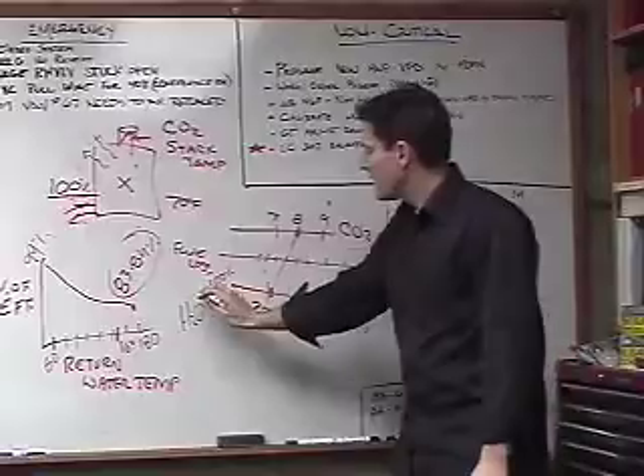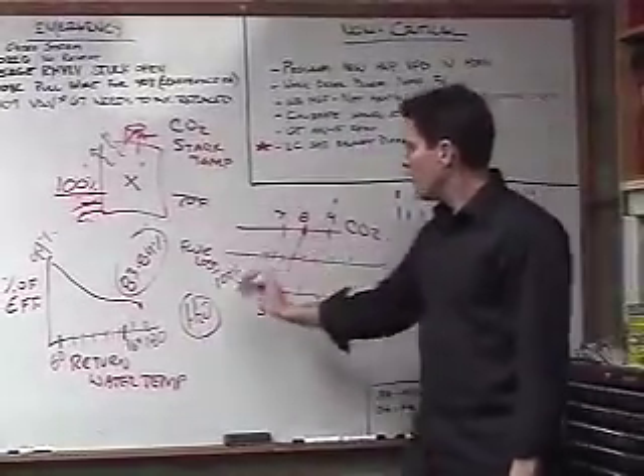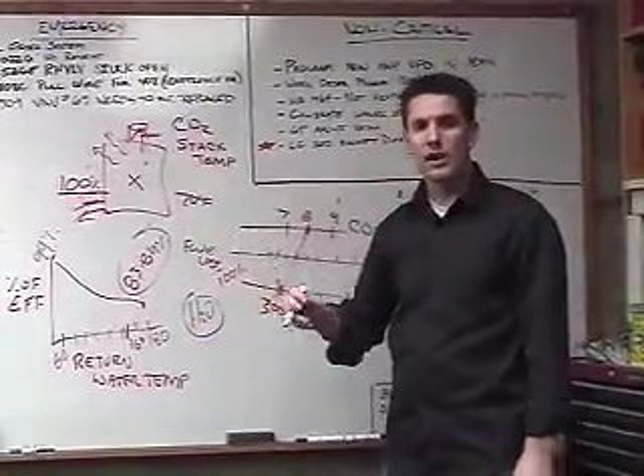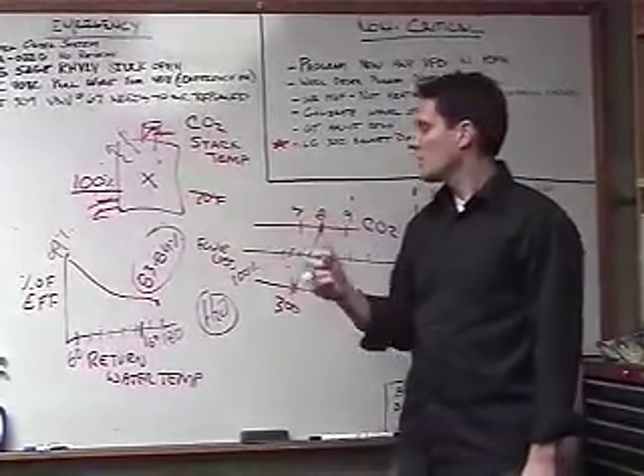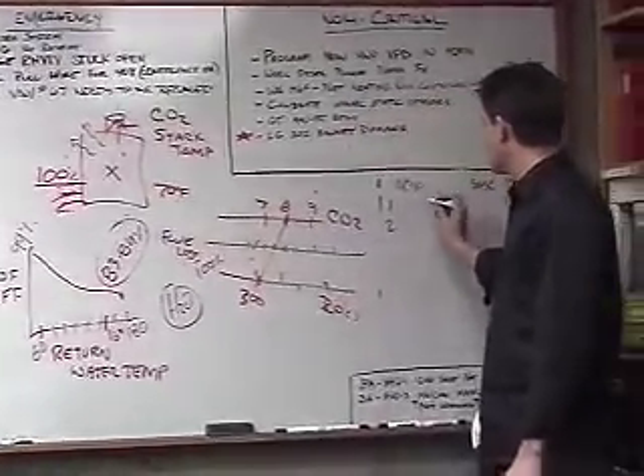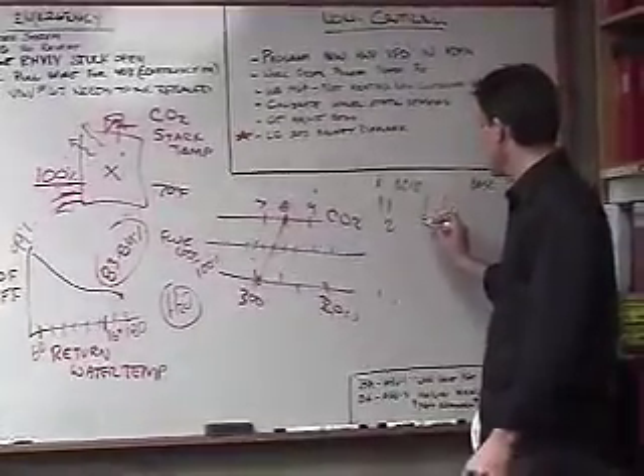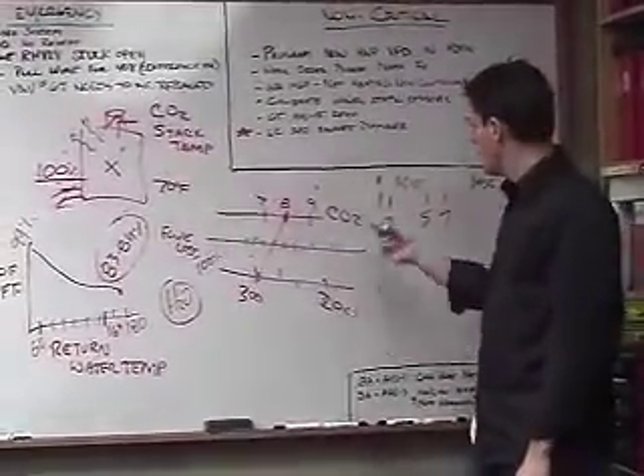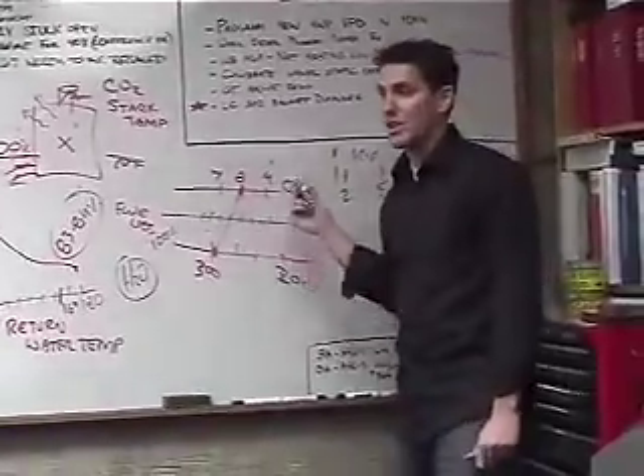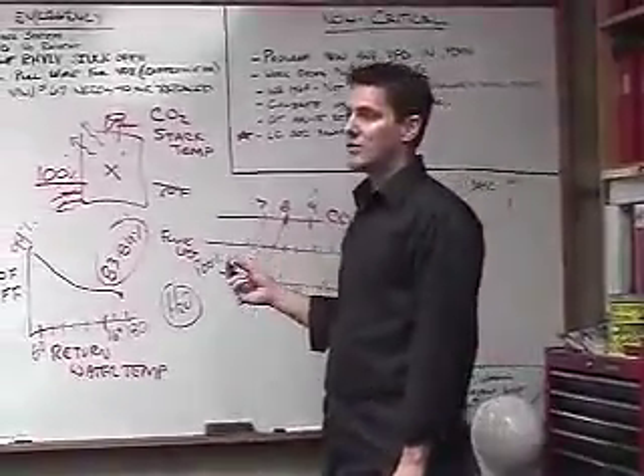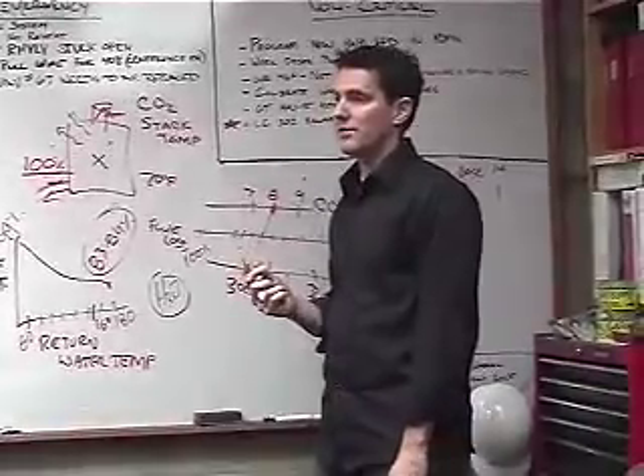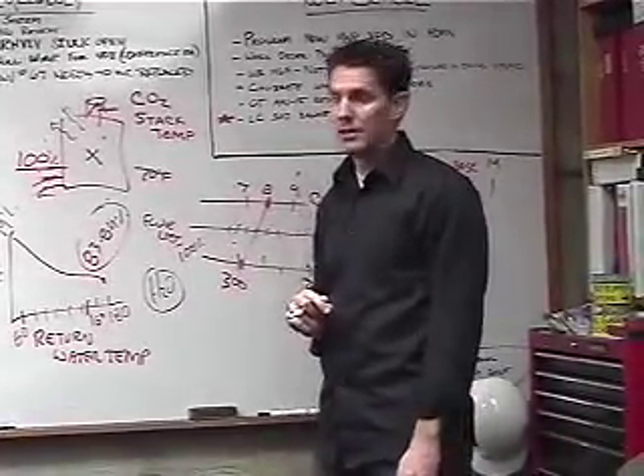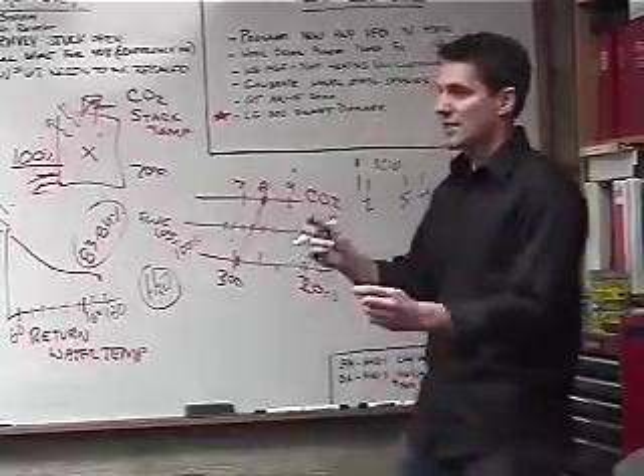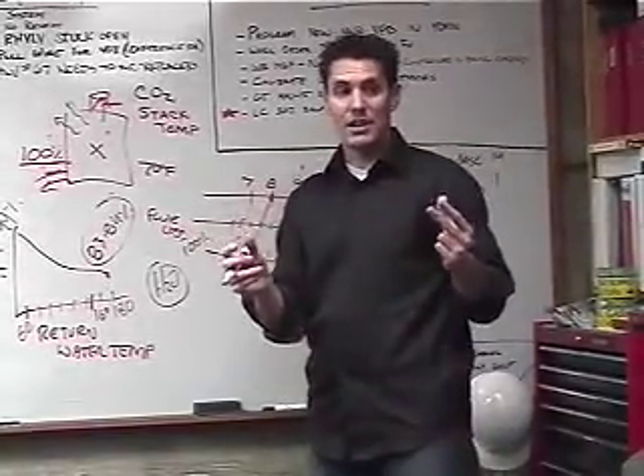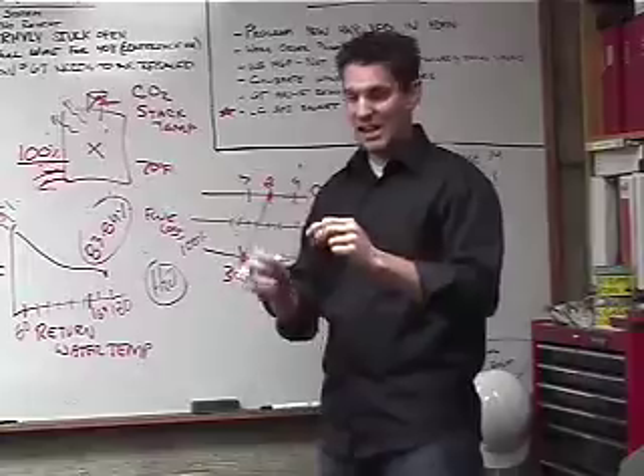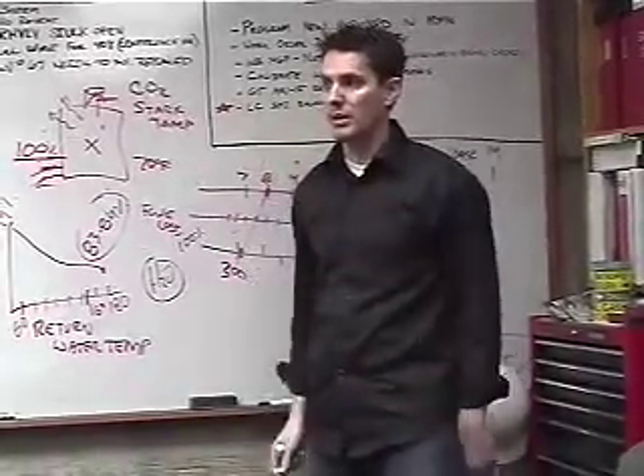All this water vapor that we create, normally water vapor wouldn't be corrosive, but we have a lot of carbon in here, so we're forming a carbonic acid. As we form this condensate, in the first pass it comes out at about 5. You're already an acid. So if you put this on cast iron, copper, or steel, it will eat through that metal. I've seen copper tube boilers fail within 2 months, because copper is very thin. I've seen cast iron sectionals that are 1/4 inch thick last 30 years, but you open those boilers up and they've been condensing and there's very little left. It's all rusted out.